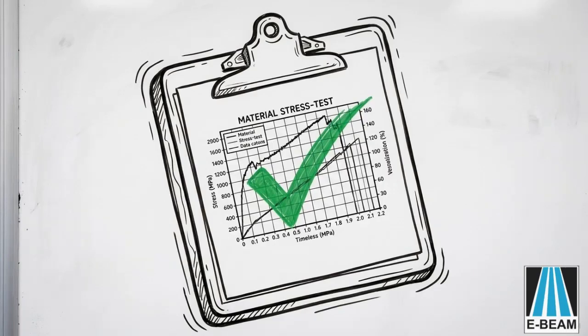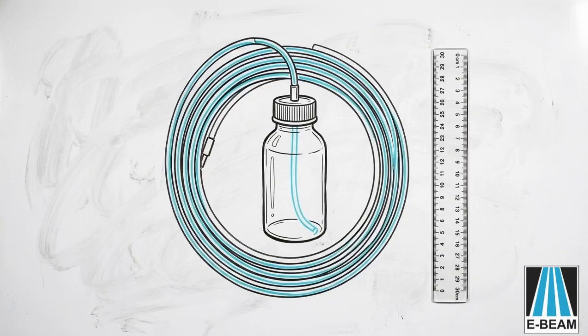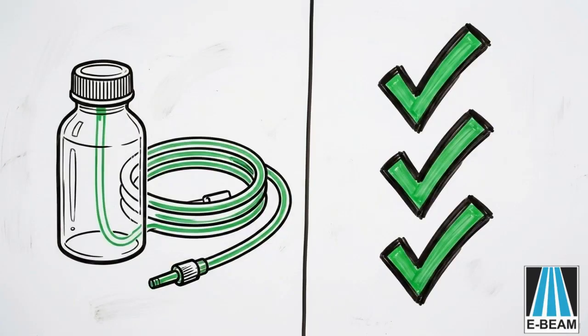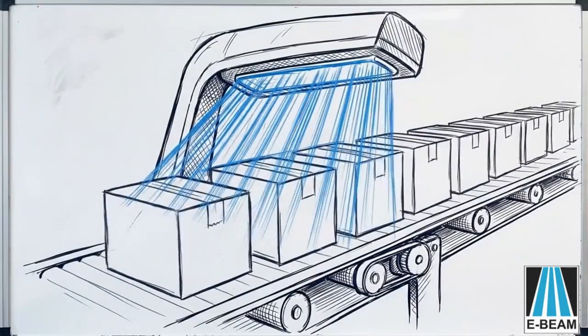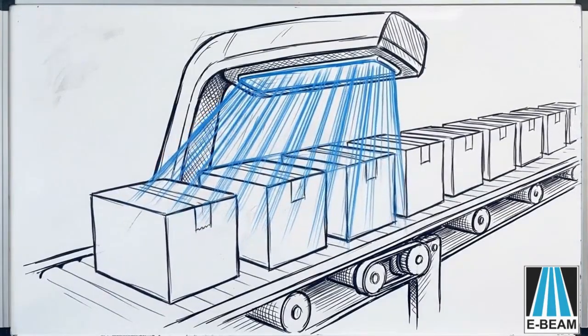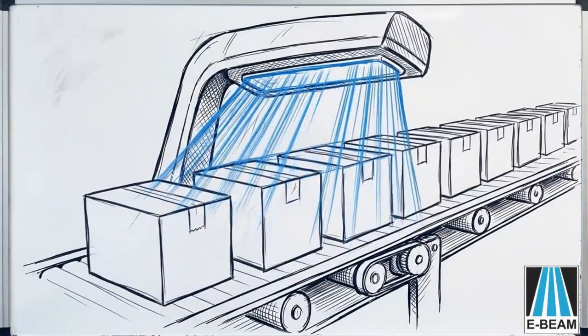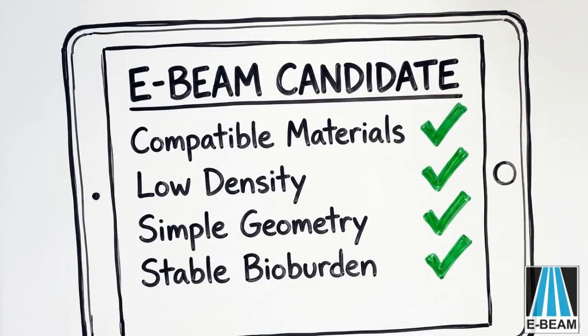The materials had well-documented radiation compatibility. The product was low density with simple geometry. Packaging could be oriented consistently, and the bioburden profile was stable, which is exactly what you want for dose-based validation under ISO 11137. When you see a list like this, ebeam isn't a long shot. It's a logical next step.